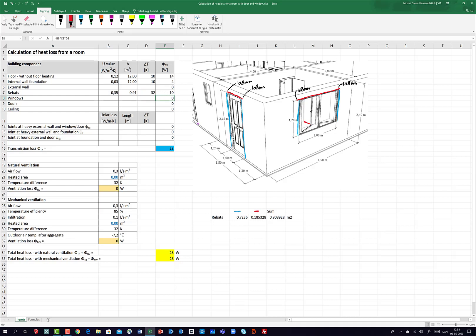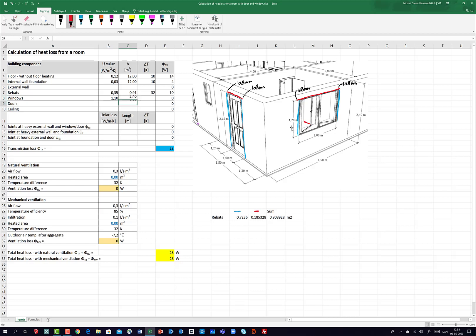Then I take the window. The U-value for a window you can look up on the producer's website; I'll use a fictive value of 1.1. The area of the window is 1.20 multiplied by 2 meters. The temperature difference is 32 Kelvin, as before — 20 inside and minus 12 outside. So I have 84 Watts through the window.